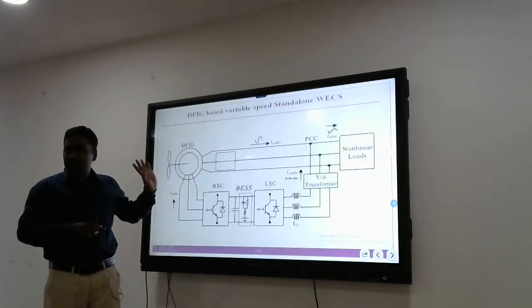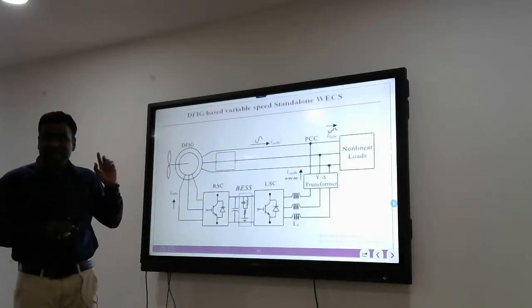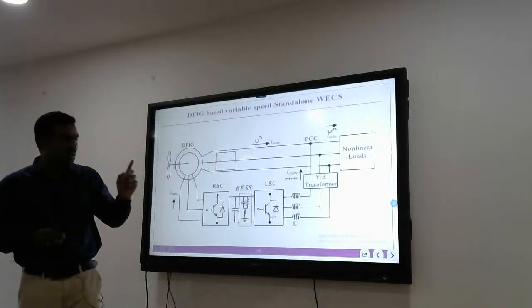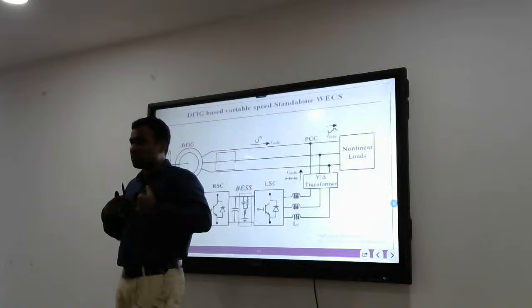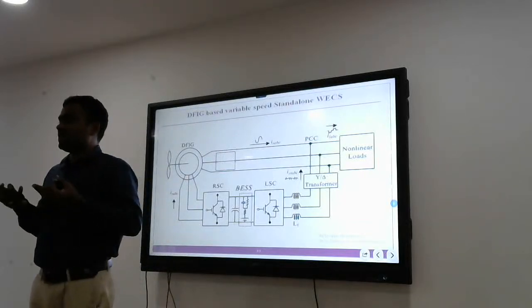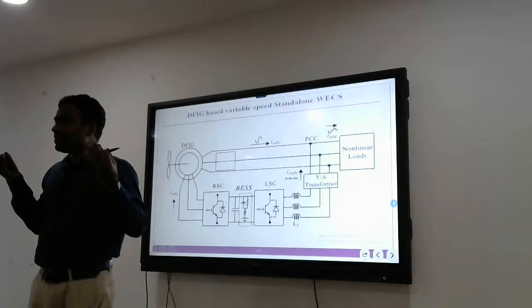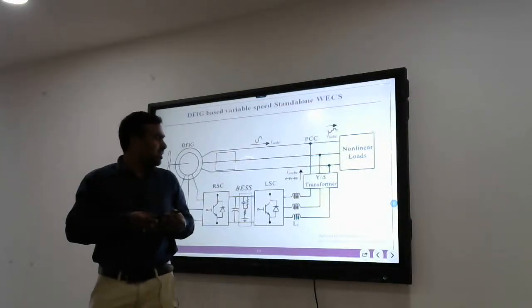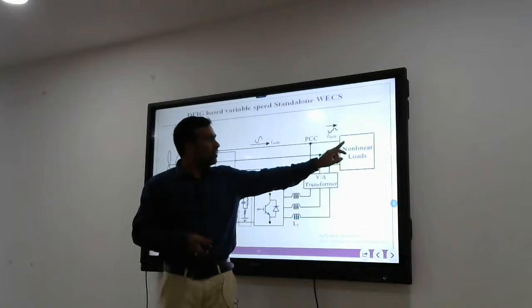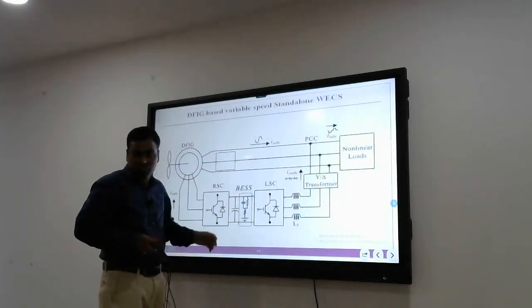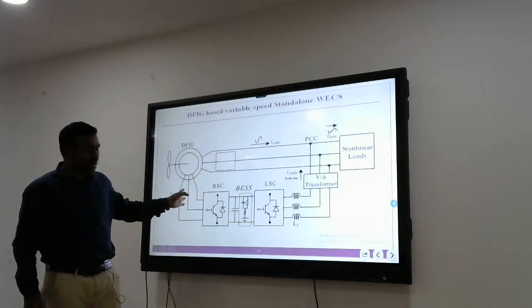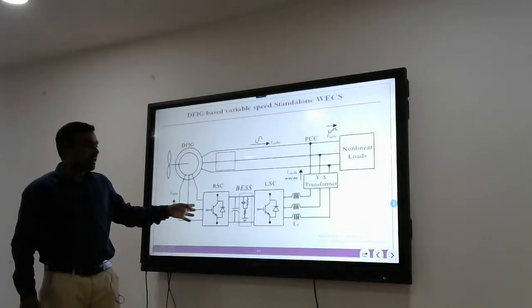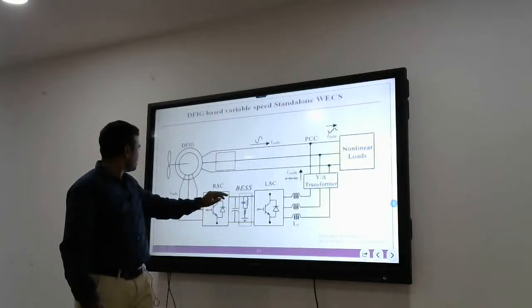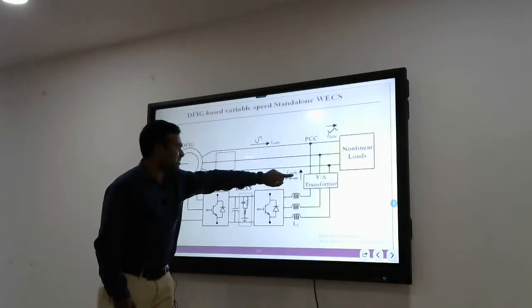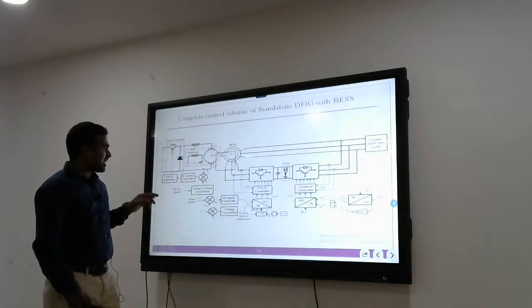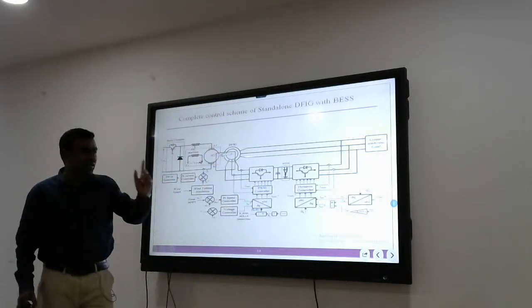In the previous case, whatever we have discussed is for grid connected mode, but here it is standalone, which means this was connected to a load. Here there is no grid, so now our responsibility is to maintain the voltage. Previously the voltage was maintained by the grid and we were injecting the current, but in standalone you have to maintain the voltage. That is one more job it has to do, but it need not have any PLL type of structure. So again the same thing, but instead of grid we have load. The control here is maintaining the voltage.